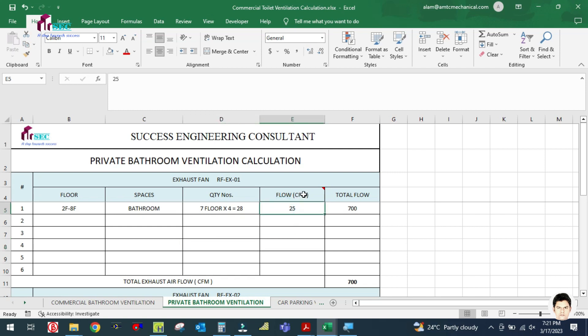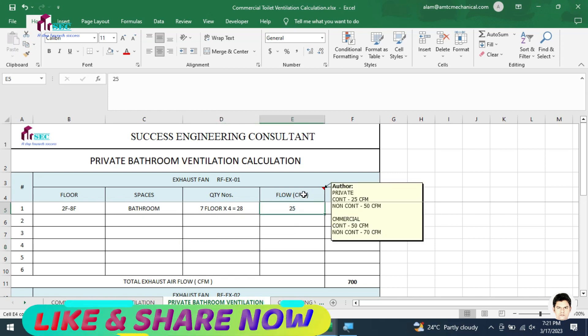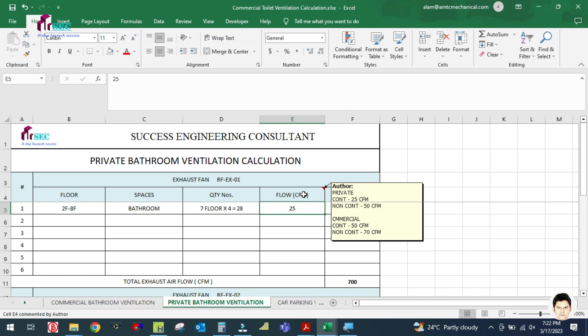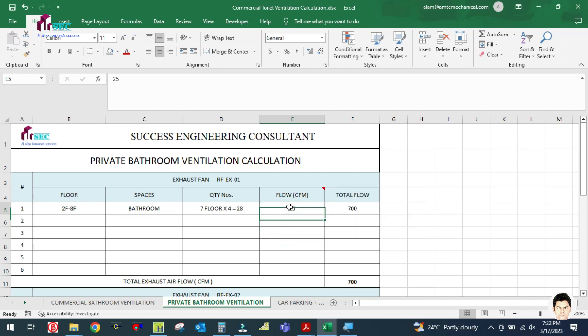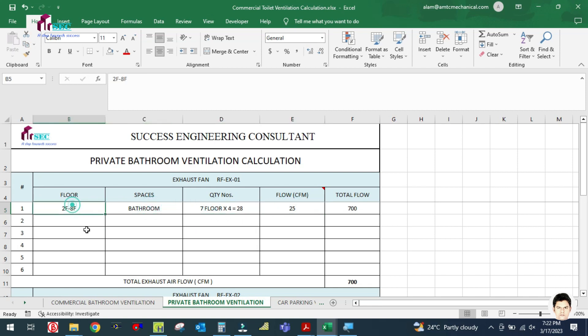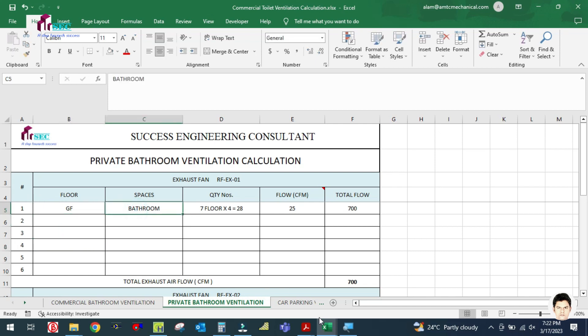For the private toilet, we are taking one toilet as per the ASHRAE ventilation standard: 50 CFM if the fan is not running continuously, or 25 CFM if the fan is running continuously. So we are assuming 25 CFM here.